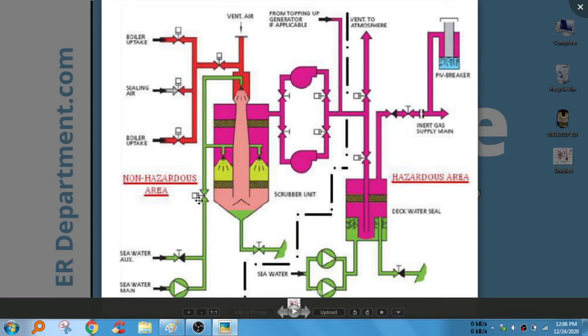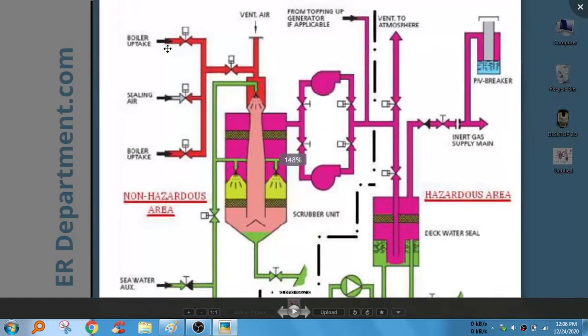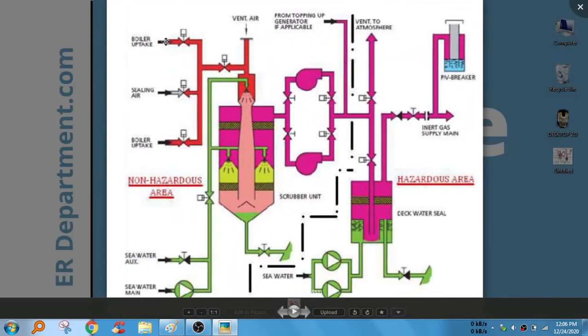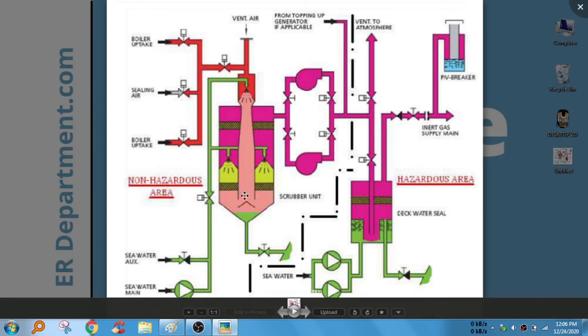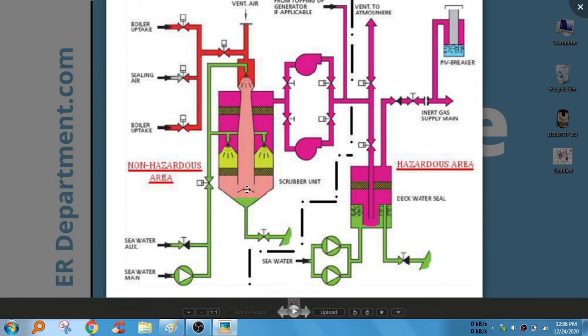Here it is shown inert gas system. Let's start from here, from boiler uptake. That means we will collect flue gases from boiler which will be hot and dirty, and it will be passed through this scrubber tower. This tower, it's not a tank, it's a tower, it's three to four meters long. Here you can see we are supplying sea water from here, and the gases and sea water go together, and the temperature of this boiler flue gas reduces.